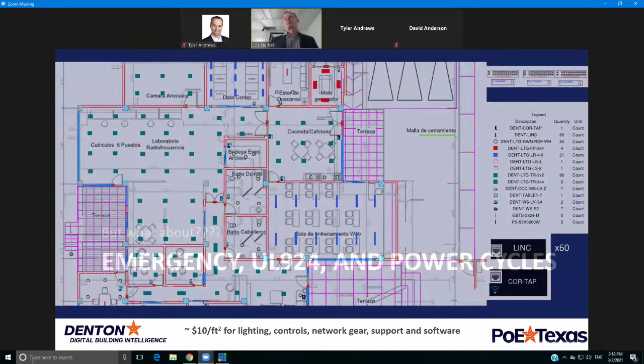We always get asked about emergency, UL 924, and power cycles. Would love to have a more in-depth conversation, but here's a quick highlight: we advertise and recommend two network stacks, one that's UPS backed and one that is not, giving you the flexibility of choosing which fixtures are UPS backed. This is a substantial advantage over a traditional hardwired conduit system, because we can just swap Cat5 cables from one stack to the next.